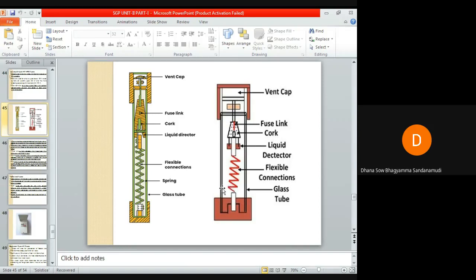So within the glass tube, one end of the fuse wire is sealed to one end of the tube, and the other end of the fuse wire is held by a strong phosphor bronze spiral spring fixed at the other end of the glass tube. So this is the fusing element, which is held in position by one end of the tube, and the other end is held in position by the spring, a strong phosphor bronze spiral spring.